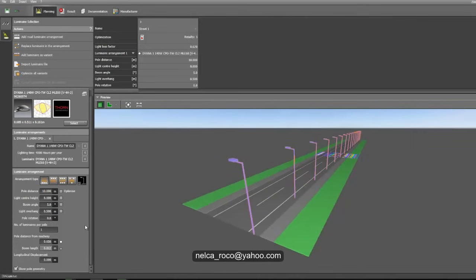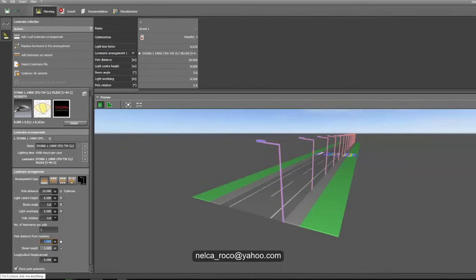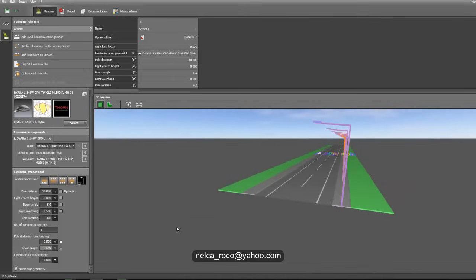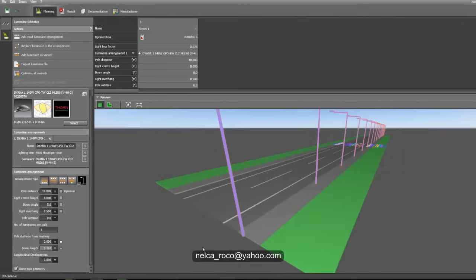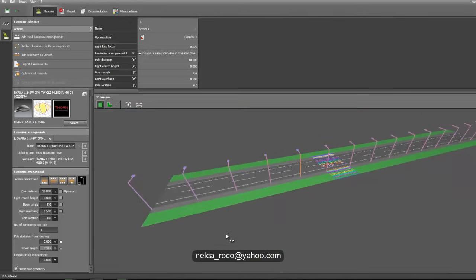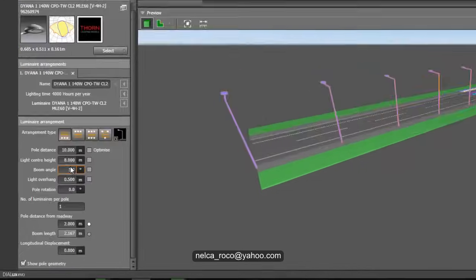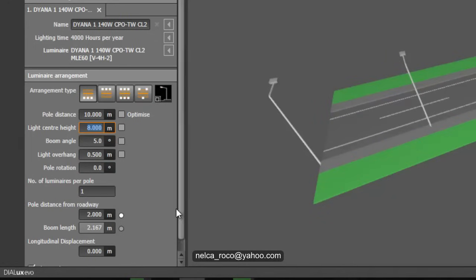Set the distance from the roadway to 1.5 meters so it's on the footpath. Actually 1.5 isn't ideal — let's try 2.5 meters. That's not good either since it's in the middle of the path walk, so let's set it to 2 meters. Now it's 2 meters away from the main road line. The opposite offset from the path walk is 0.5 meters. We have 10-meter pole spacing. Now what should the height be? Let's set it to 8 meters.